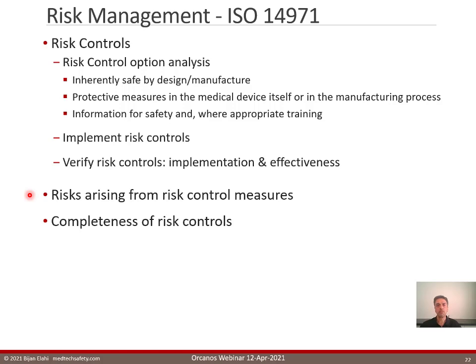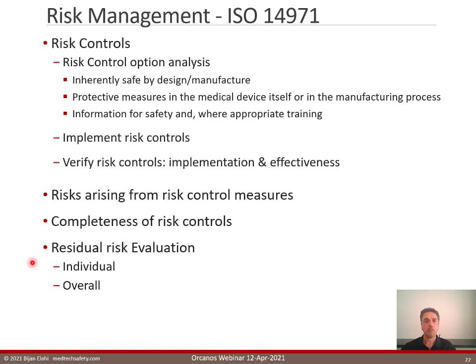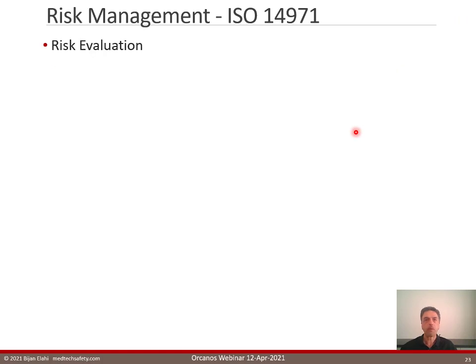Next, we need to check for completeness of risk controls. And this means we need to ensure that all the risks that have been identified have been controlled. Nothing fell through the cracks. And we need to do residual risk evaluation. At this point, we have individual risks identified and estimated, so we need to evaluate those, but we also have to do an overall residual risk evaluation. After risk controls are done, the risk that remains is called residual risk. There are individual residual risks. These are for each hazard and hazardous situation, and collectively they create an overall residual risk for the whole device. The standard requires the evaluation of the individual residual risks and the overall residual risk.